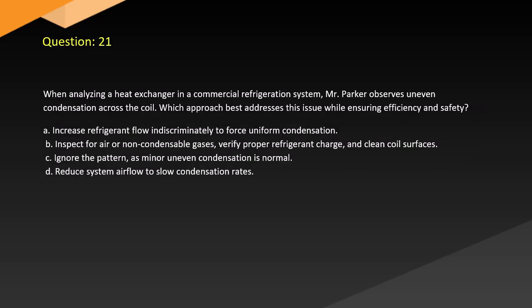Question 21. When analyzing a heat exchanger in a commercial refrigeration system, Mr. Parker observes uneven condensation across the coil. Which approach best addresses this issue while ensuring efficiency and safety? A. Increase refrigerant flow indiscriminately to force uniform condensation. B. Inspect for air or non-condensable gases, verify proper refrigerant charge, and clean coil surfaces. C. Ignore the pattern as minor uneven condensation is normal. D. Reduce system airflow to slow condensation rates.